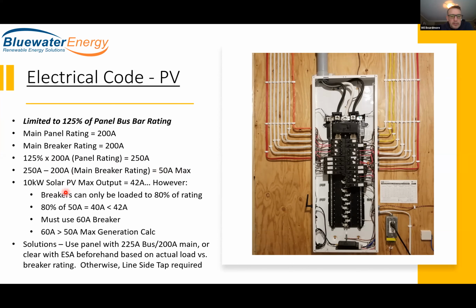Now, a 10 kilowatt solar inverter is going to output 42 amps, which, if you look at that, you say, great, we're under 50 amps, no problem, let's go. Well, the issue here is that breakers can only be loaded to 80% of what they're rated for. So if we're going to connect 42 amps on the next size up breaker, which is 50 amps, a 50 amp breaker at 80% can actually only be connected to a maximum 40 amp load.